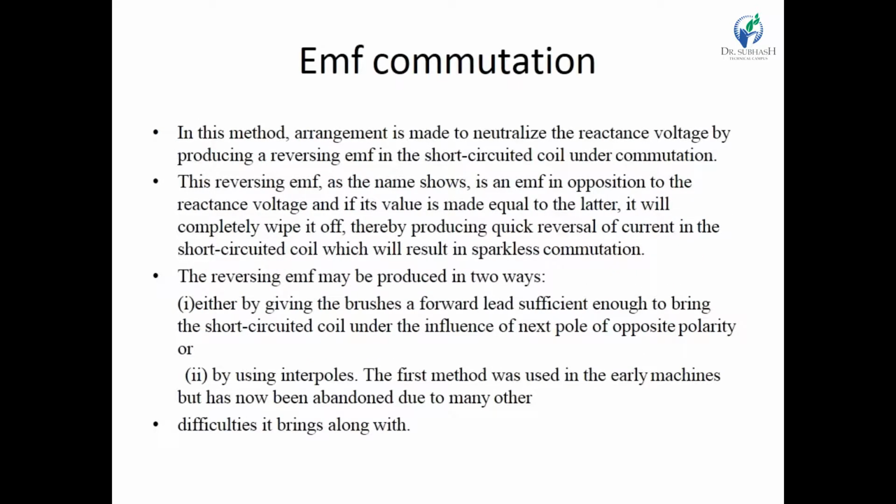Now we go to the EMF commutation. EMF commutation is a technique used to neutralize the reactance voltage by producing a reversing EMF in the short-circuited coil under commutation. The reversing EMF is in opposition to the reactance voltage, and if both voltages are equal, then the effect of the reactance voltage can be completely wiped off. We can then achieve ideal commutation.